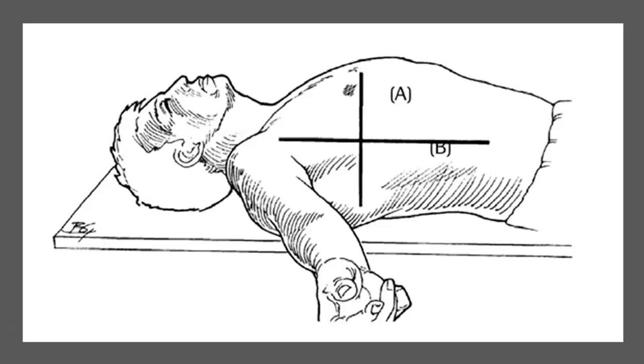So we want them at least head of bed 30 degrees or higher, okay? But if we raise them any higher or put them down flat for whatever reason, we have to move that transducer for that invasive hemodynamic line when we move the patient. Otherwise, it is not accurate. It's got to be moved, re-zeroed, and recalibrated to ensure that it's accurate.